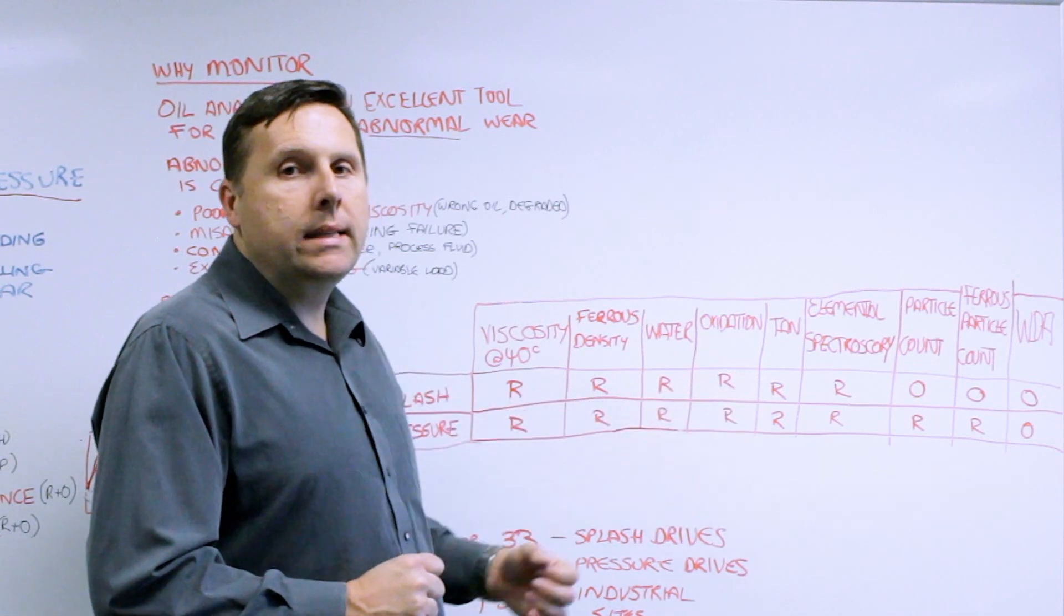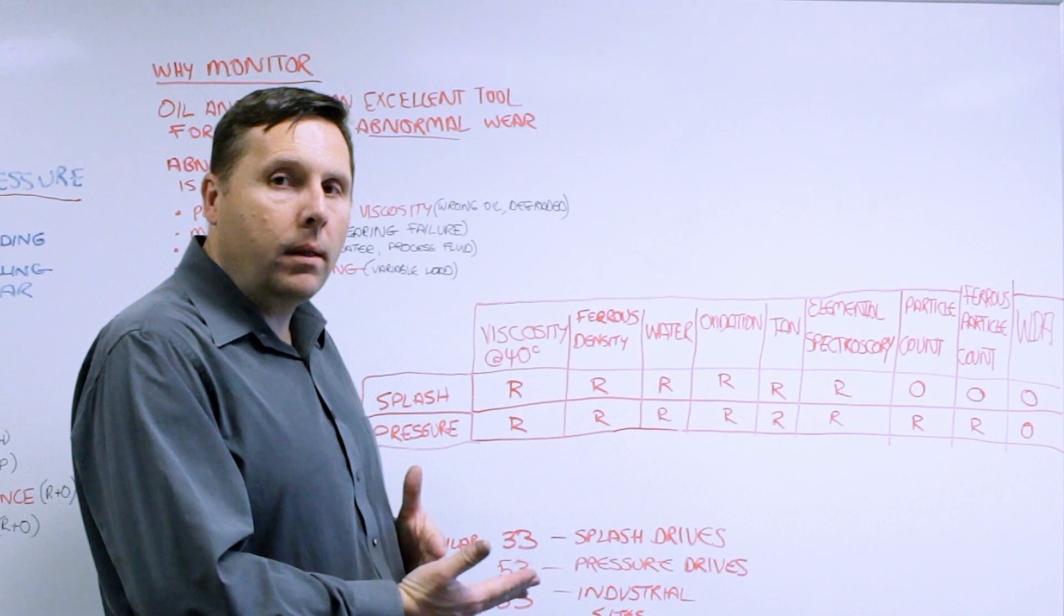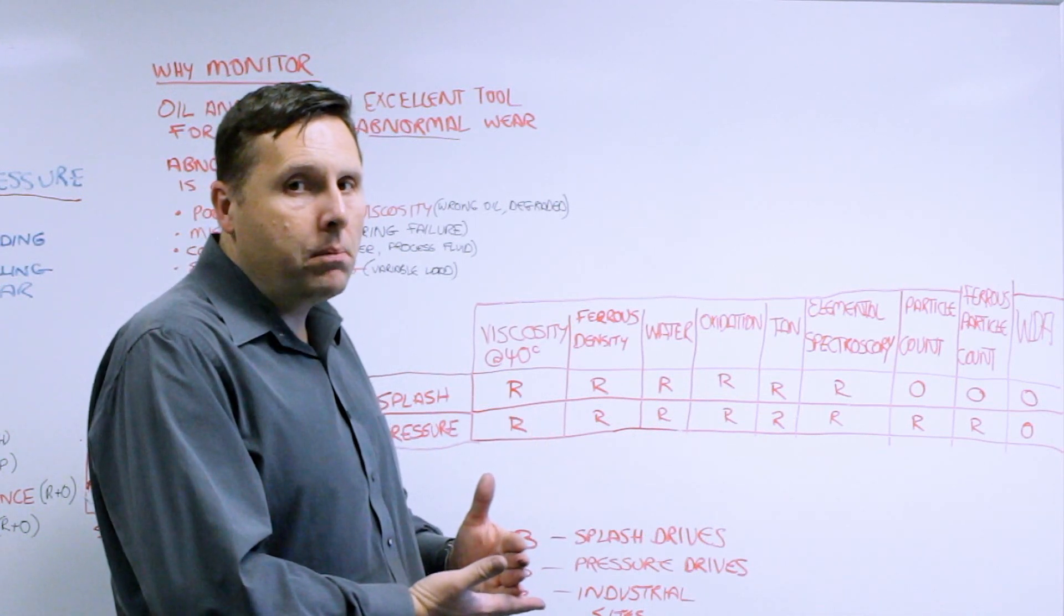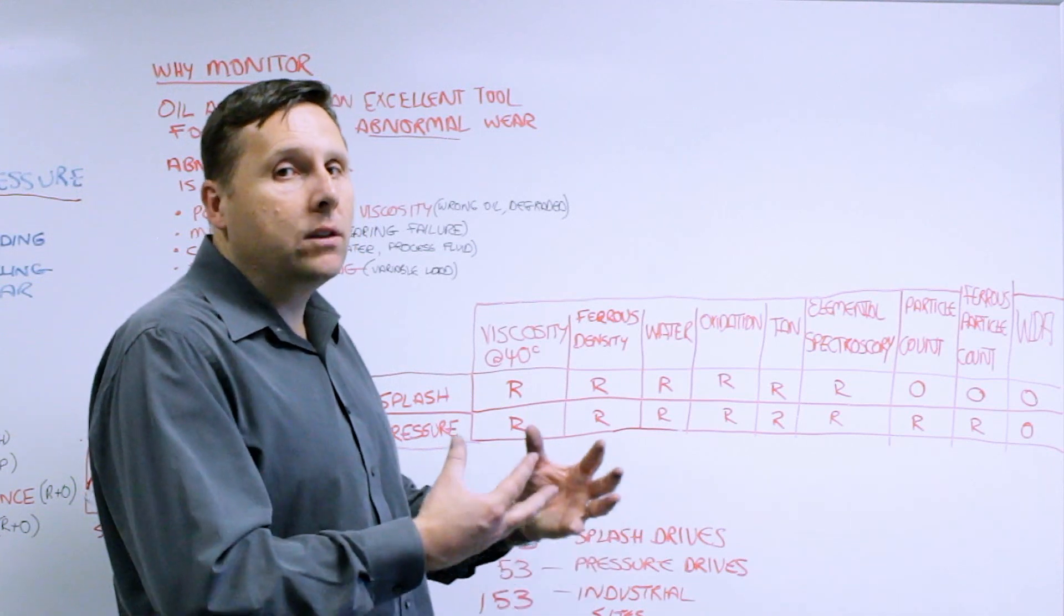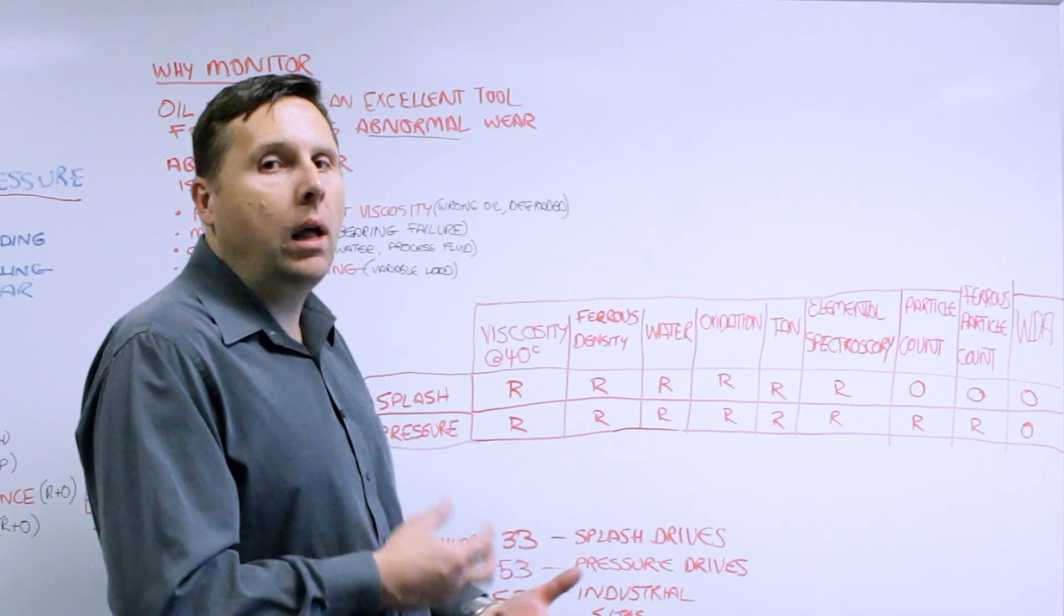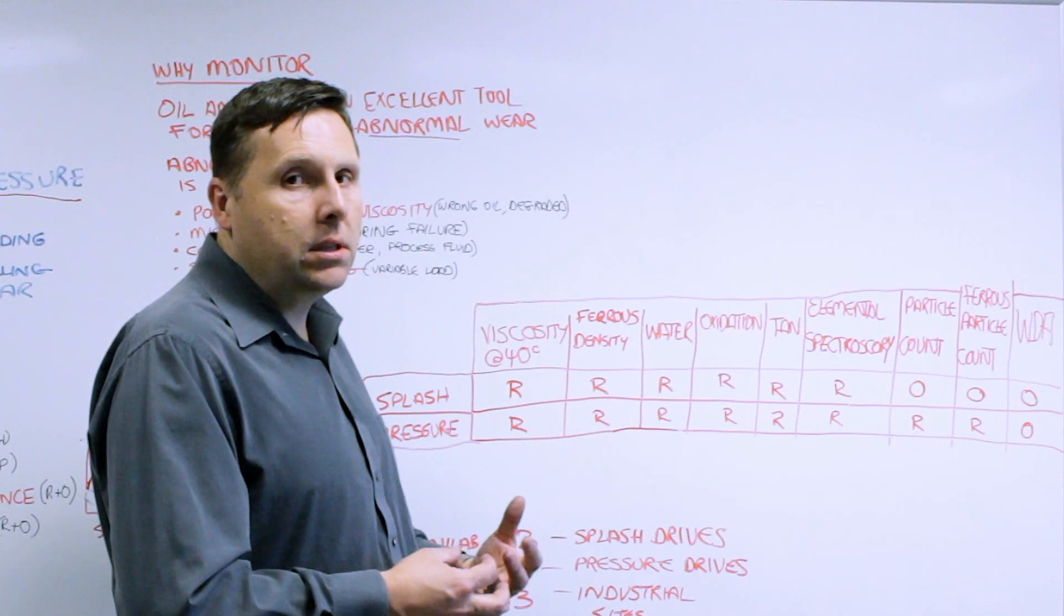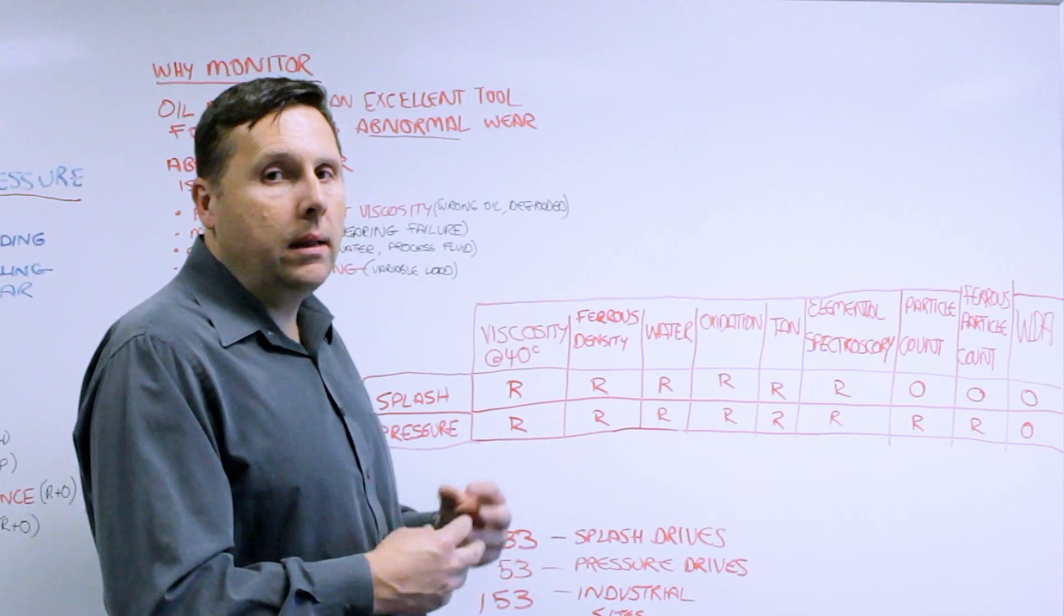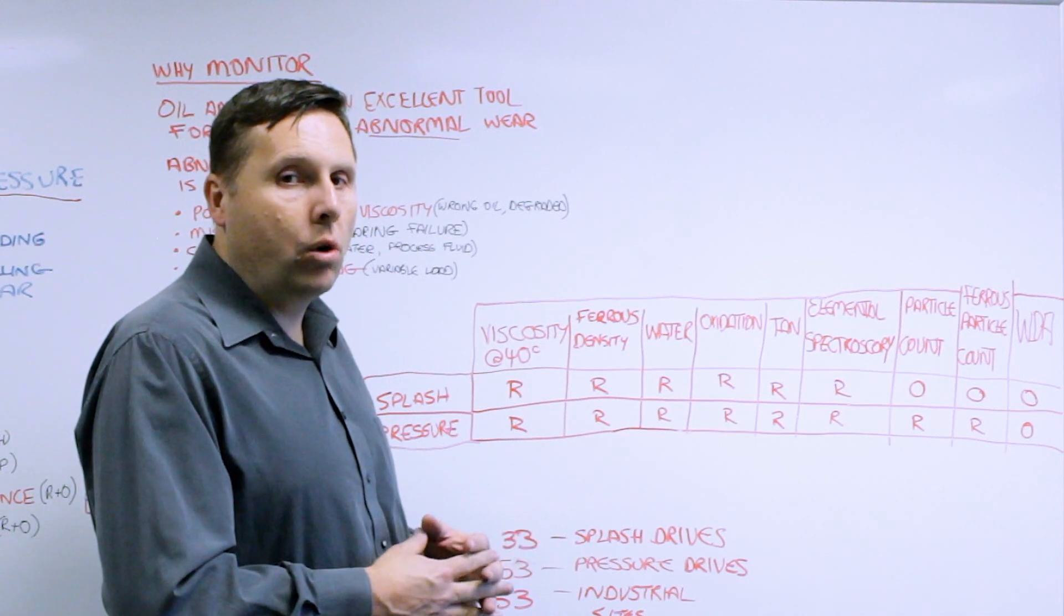Elemental spectroscopy is excellent for looking at the additive elements that are present as well as the very fine wear that's being produced, ferrous wear, as well as the non-ferrous wear that can be common in a lot of gear systems especially with bearing supports as well as in sacrificial gear systems such as worm gears.